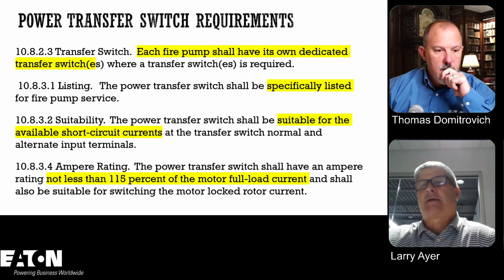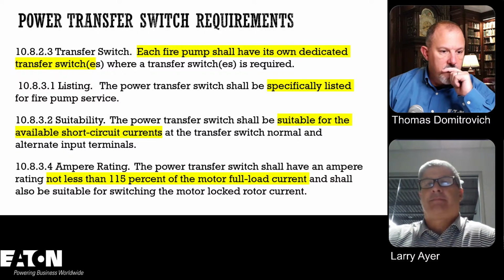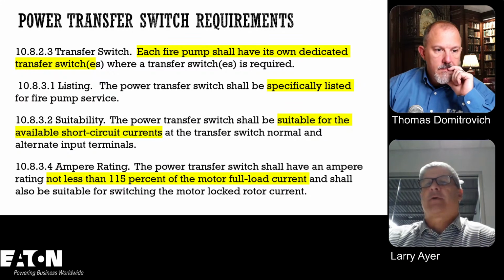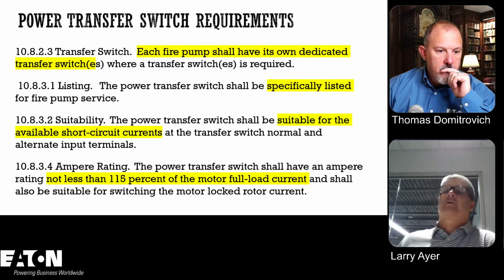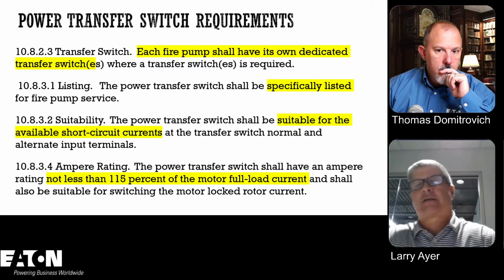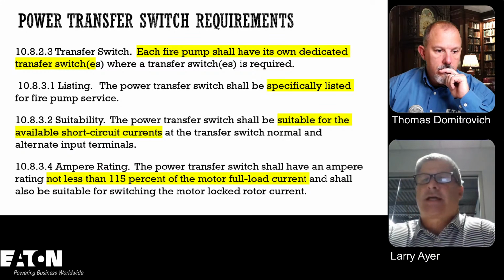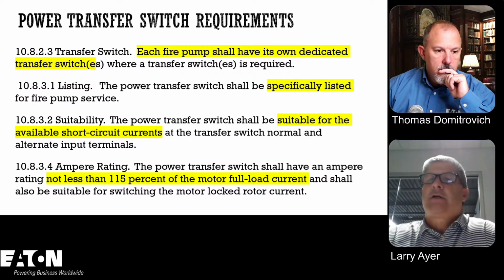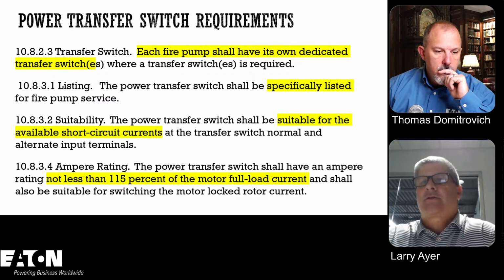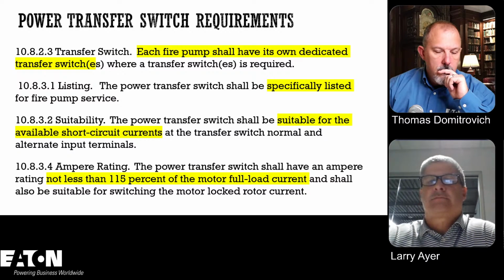The last one, ampere rating, is a little bit unique in that the power transfer switch shall have an ampere rating not less than 115% of the motor full load current. So it doesn't have to be at 125%. It strictly has to be at 115%. But you've got to watch it, because depending on what type of transfer switch you pick, you might have to oversize the transfer switch to meet certain requirements in the NEC.